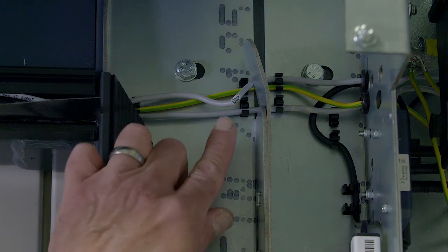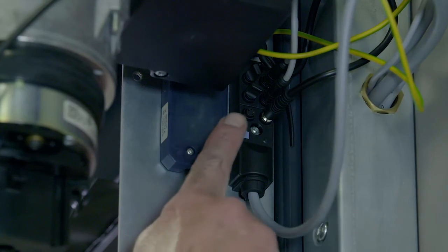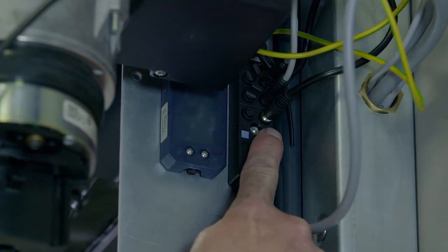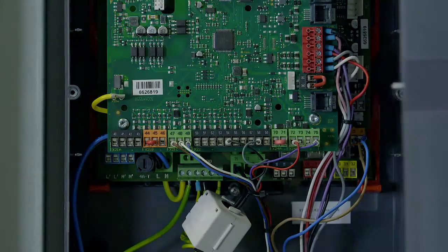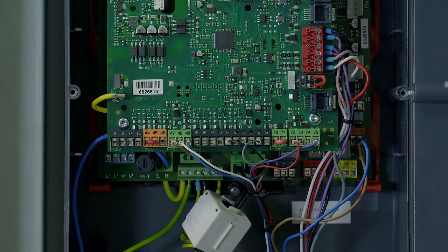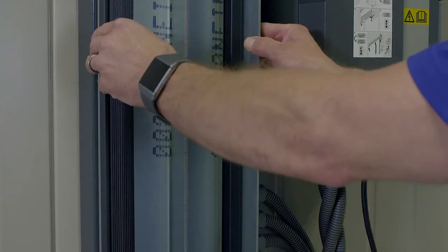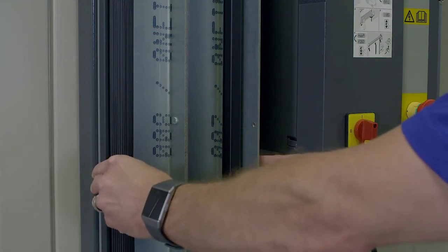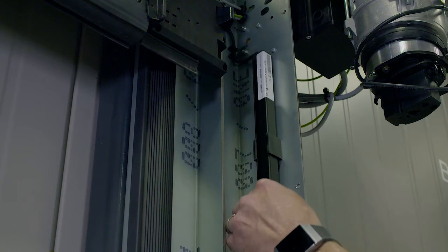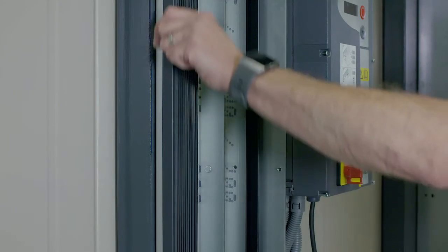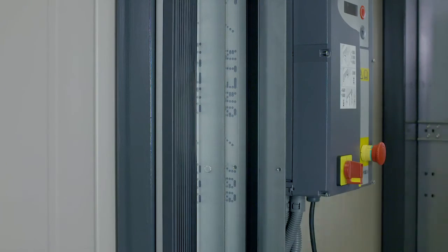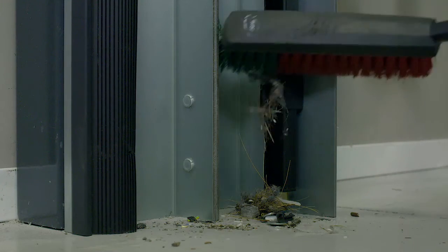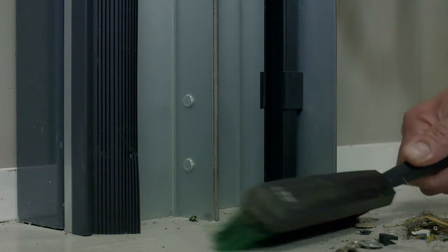If the LEDs aren't showing as expected, check the following to identify the problem. There might be a faulty or damaged cable. The cable could be plugged into the wrong location on the SNAP8 block. It could be incorrectly wired in the control panel or there could be a problem with the control panel. It could be that the leg is out of line or that the light grills are at different heights. It might be that the light curtain is interrupted by a side seal that is damaged or loose. The light grills could be activated by dust, dirt or debris. It could be that the light grills themselves are faulty or damaged.